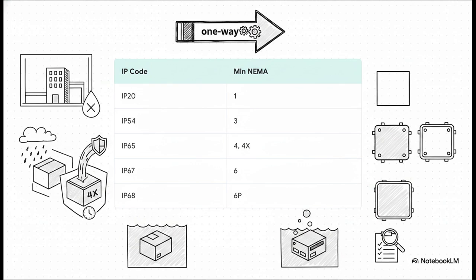For example, an IP20 maps over to a NEMA 1 enclosure, perfect for indoors where you aren't worried about water. IP54 maps to NEMA 3, which keeps out falling rain and sleet. And IP65 maps up to a NEMA 4 or 4X, bringing in special gaskets for washdown situations. Then IP67 takes you to NEMA 6 for temporary immersion, and IP68 brings us all the way to NEMA 6P for prolonged underwater submersion. But remember, you always have to double-check these minimums against what your specific application actually needs.